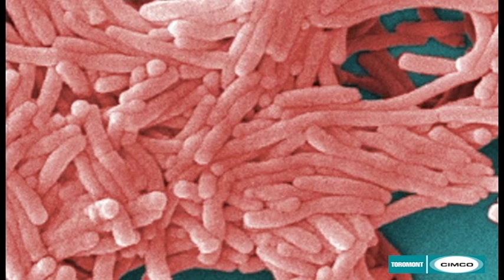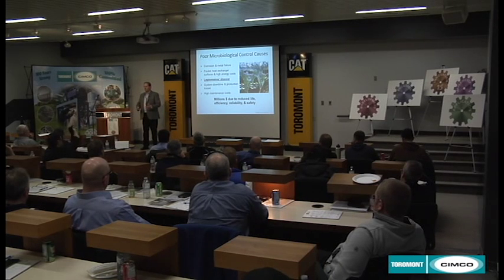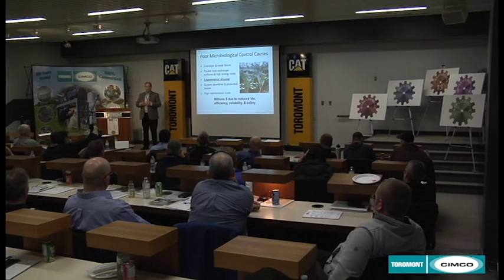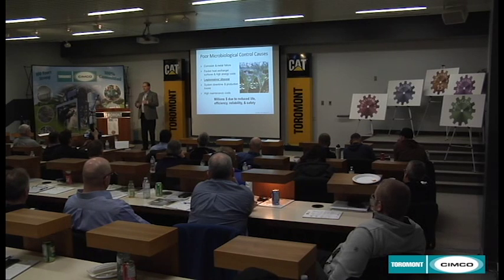Legionnaire's disease is a bacteria that grows in your cooling tower. You cannot stop it. You cannot kill it. You could control it. Basically what happens is that the Legionnaire bacteria lives in lake waters. The city treats water to provide to us to drink, but they don't kill Legionella bacteria. Legionella bacteria is not one of the components that people will drink and get sick on, so they don't look at it, they don't guarantee that they control that Legionella. Once that Legionella bacteria grows into your cooling tower, which is the perfect media for Legionella to proliferate and actually multiply and get bigger and bigger.